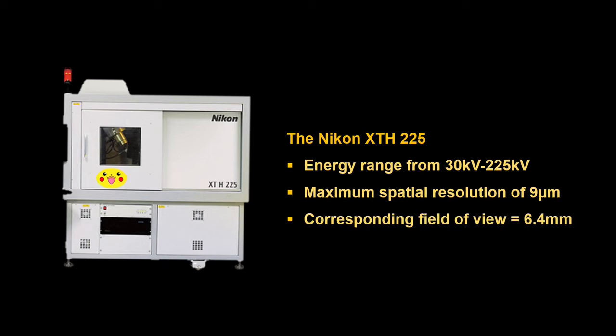The maximum spatial resolution of the Nikon is 9 microns. So features down to 9 microns you can see. In order to get to this maximum spatial resolution, the corresponding field of view, or the area that you will see, is only 6.4 millimeters. So for samples that are larger than 7 millimeters, you won't be able to have the highest resolution over the entire volume.